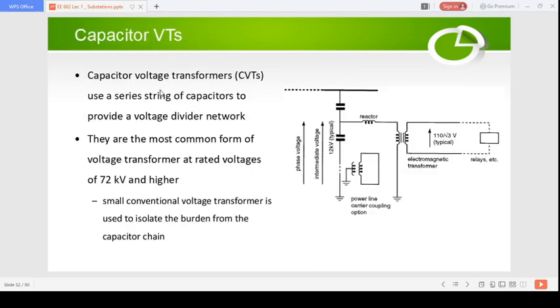If the voltage is higher than 36 kV, it is cost effective to use the capacitor type voltage transformer. They use a series string of capacitors to provide a voltage divider network. As shown here, instead of magnetic or electromagnetic coupling, you now have a voltage divider arrangement built from capacitors. These are the most common form of voltage transformers at rated voltages of 72 kV and higher. Between 36 and 72 kV you may find a mix of those, but for very high voltages these are the most used voltage transformers.